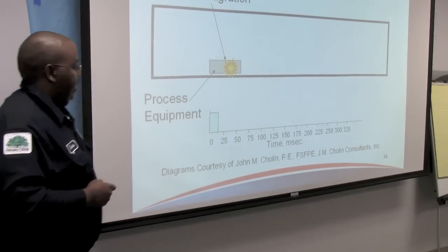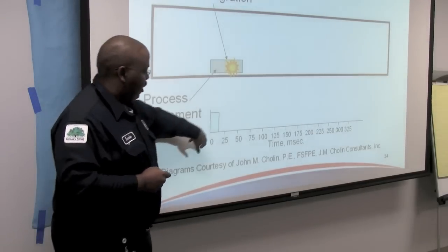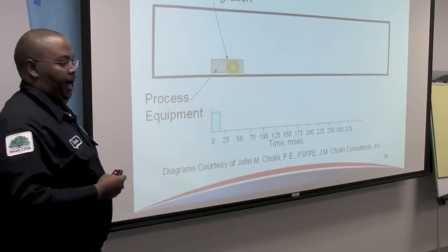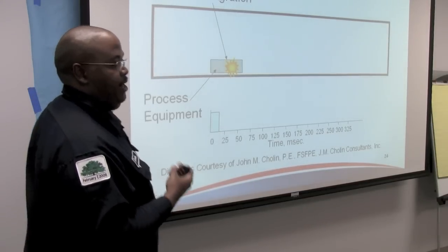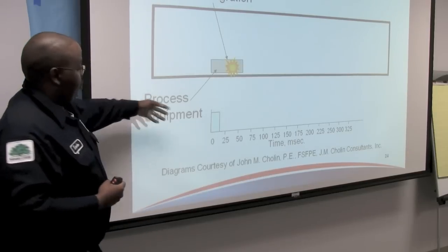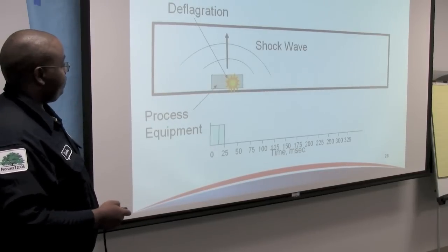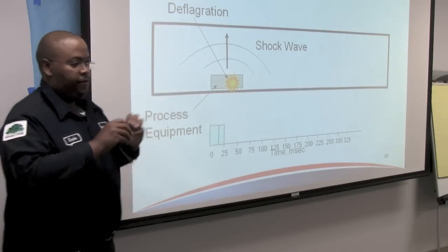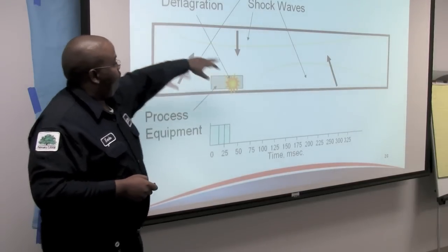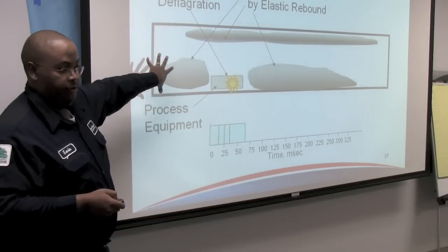When we talk about dust explosions and deflagrations, we're talking milliseconds — this stuff happens quickly. You don't have a chance to realize you're in the immediate zone. With this model: a piece of process equipment has an initial internal deflagration, it creates a shock wave with pressure moving out, and elastic rebound shock waves stir up residual dust. This is why housekeeping is so critical.